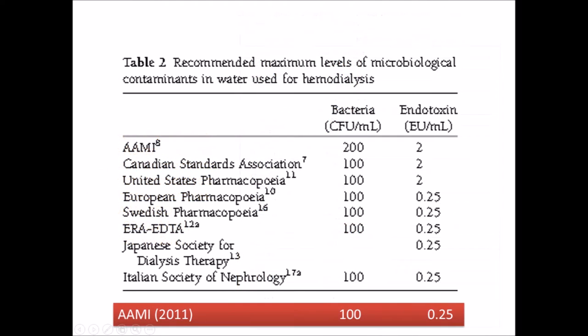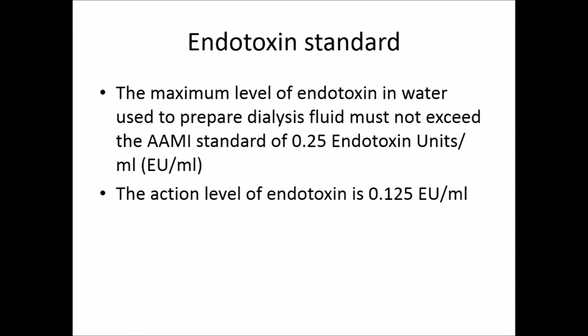The maximum recommended level of microbial contaminants follows AAMI standards 2011. The maximum number of bacteria in water used to prepare dialysis fluid should not exceed 100 colony forming units per ml, and the AAMI action level is 50 colony forming units. The action level is defined as the point at which measures must be taken to correct the potential source of contamination to remain in compliance. For endotoxin, the maximum level should not exceed 0.25 endotoxin units per ml, and the action level is 0.125 endotoxin units per ml.